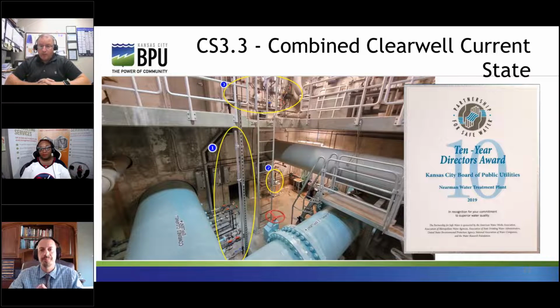In addition, all our turbidimeters were installed with individual filters, combined clear well, and plant effluent. After evaluating several turbidimeters, BPU decided to go with new Hach TU5300 and TU5200 benchtop turbidimeters. These were installed in 2020, and at this point, they have performed extremely well. The new turbidimeters are much easier to clean and calibrate, and we hope to see some savings on maintenance and calibrations. We have recently started replacing some of our online chlorine monitors as well. We hope to include those in next year's report. And most significantly are the happy operators and plant management who no longer have to deal with problems in this area of the plant.